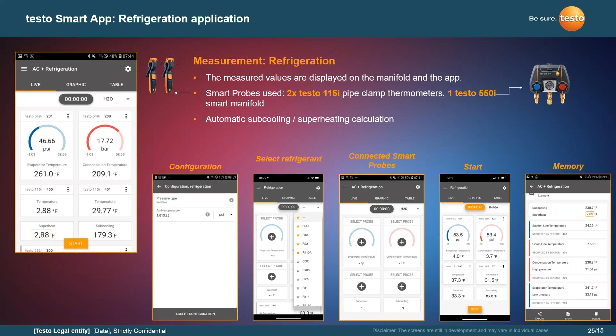So on the refrigeration side, if you're doing subcooling or superheat, it's really nothing different except you're going to be connecting in the app, okay? You're only going to have the option for wireless pipe clamps. So you would connect those 2 pipe clamps and make sure you have the right coded number on the back of the pipe clamp, whether it's high side or low side, okay? And then it would automatically calculate those readings for you.